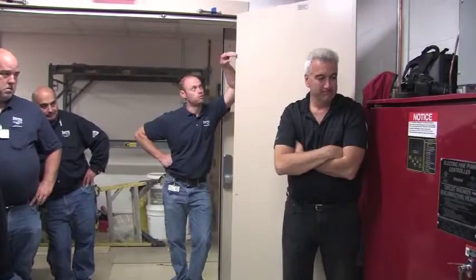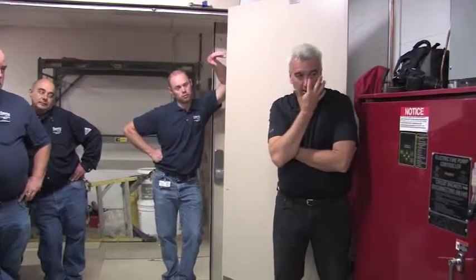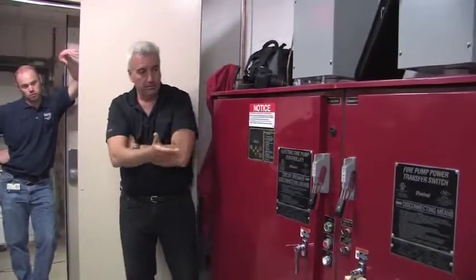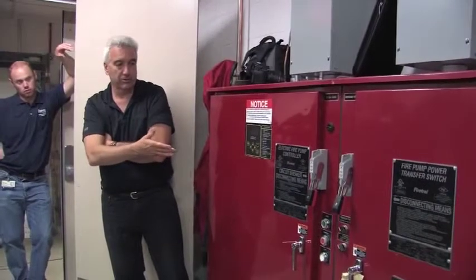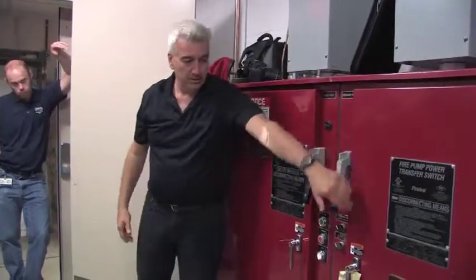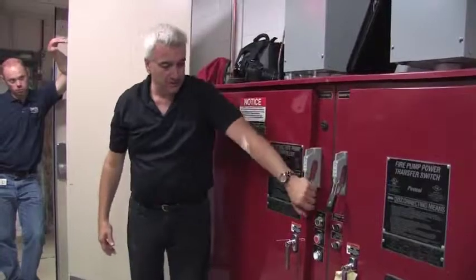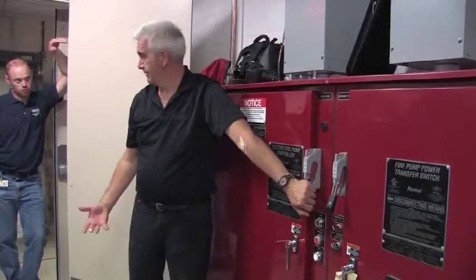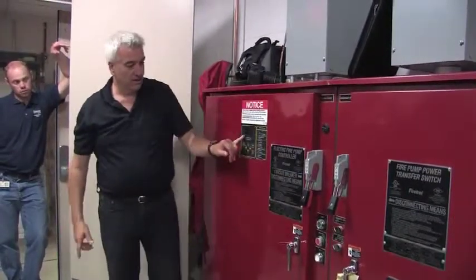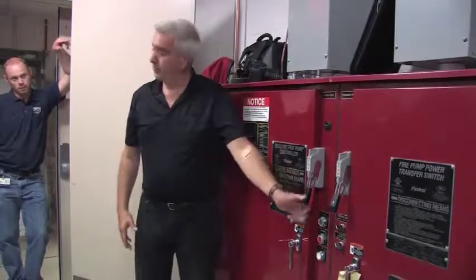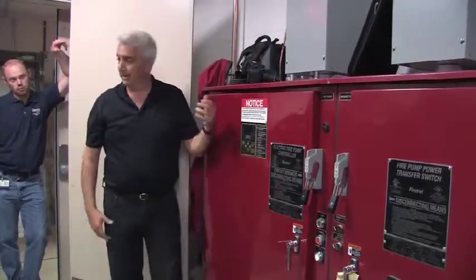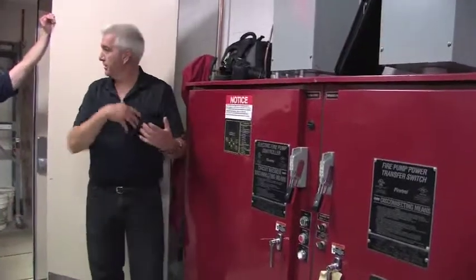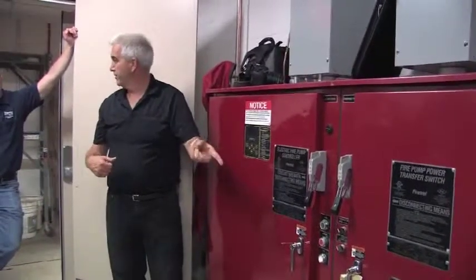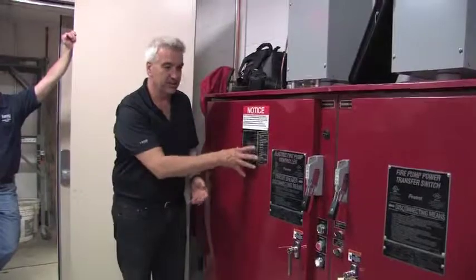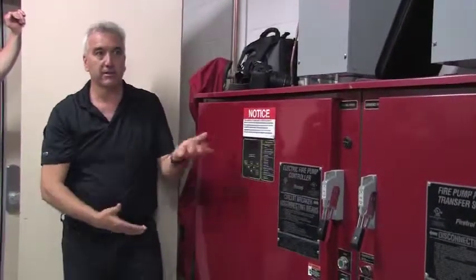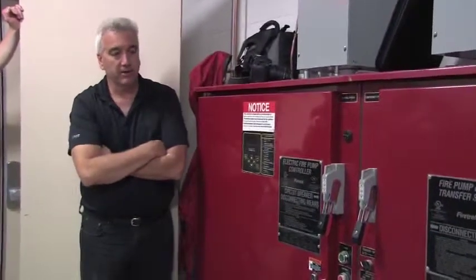And when you do, let's say you have to shut power on and off, you know the old issue with most all controllers: you need to shut off the generator power first, and then shut this one off so you don't call the generator to run by mistake. Now with these controllers, I always recommend you turn this one back on first, like you always do, but count to 10, let the electronics come up, let the lights light, before you put the other one on. That way it's not saying, oops, we don't have power. Just let it settle in for 10 seconds first. That's the only thing I recommend.